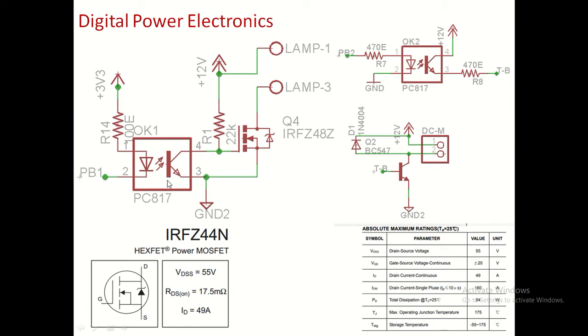That's the reason it's very important that when you are developing any power electronic application, naturally you must isolate the digital circuit, including all biomedical applications and the healthcare sector. The human interface has to be isolated from the power system by using optical communication.